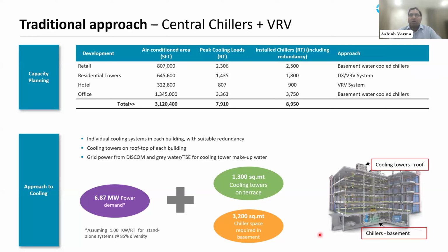The cumulative installed capacity considering the redundancy was 8950 RT, which is significantly higher than the peak cooling load. Again, these systems have the cooling towers on the top and individual cooling systems. They were relying on grid power and all those things. But the major point, if you can see here, is the power demand was 6.87 megawatt with a combination of all these cooling equipment. The assumption was 1 kilowatt per RT, considering 85% diversity, apart from the space that will be required for installation of cooling towers and the chillers.